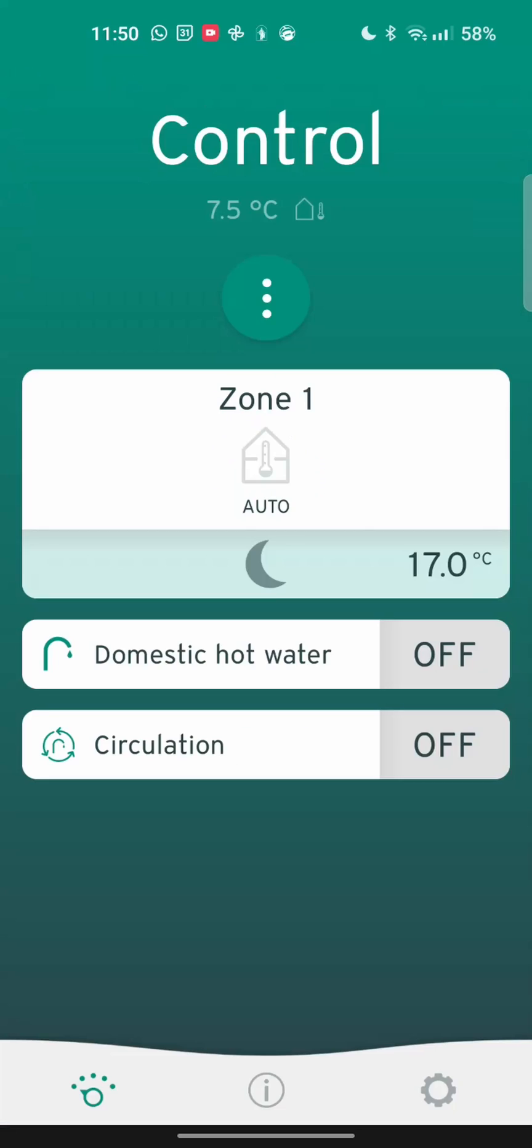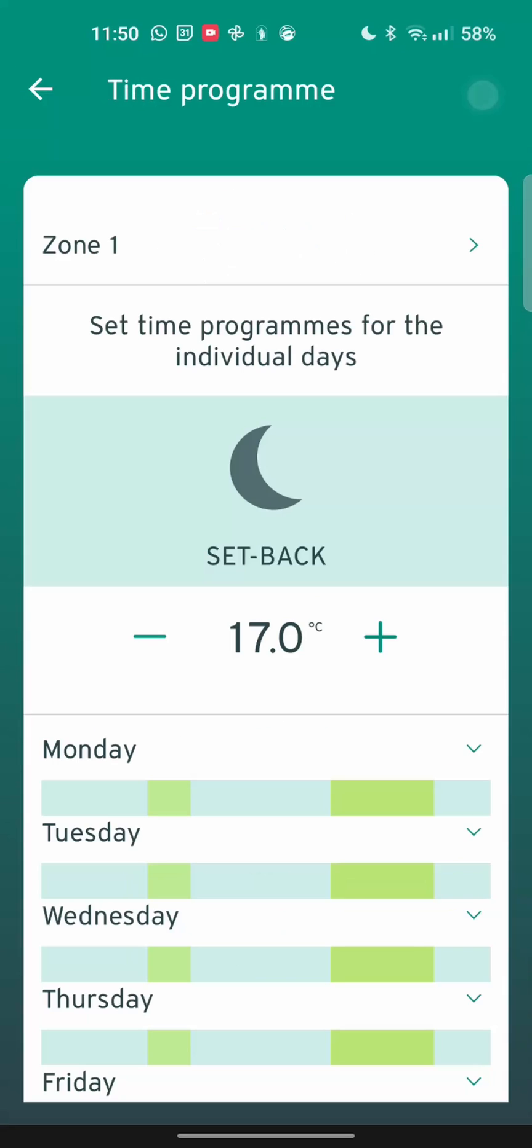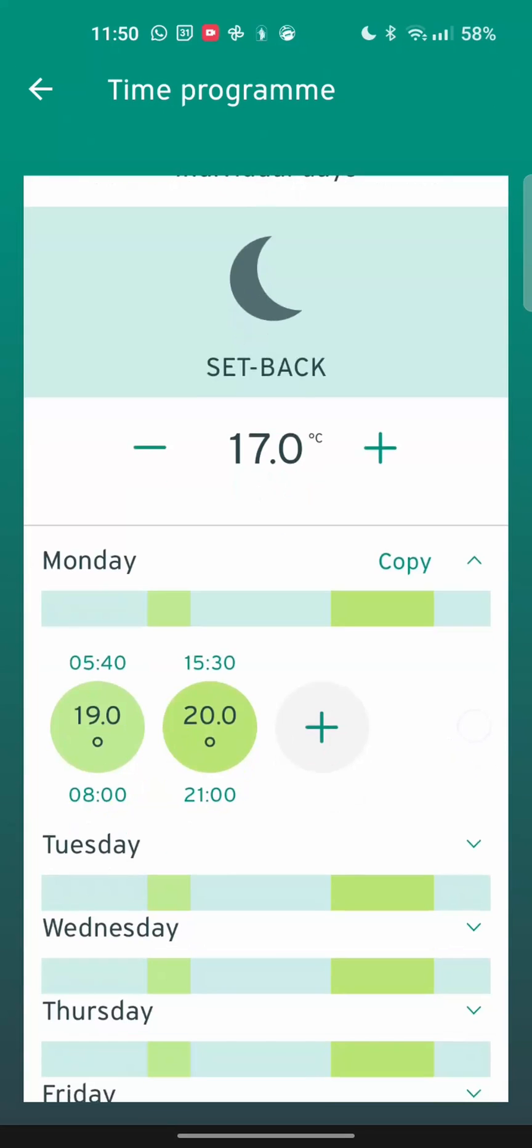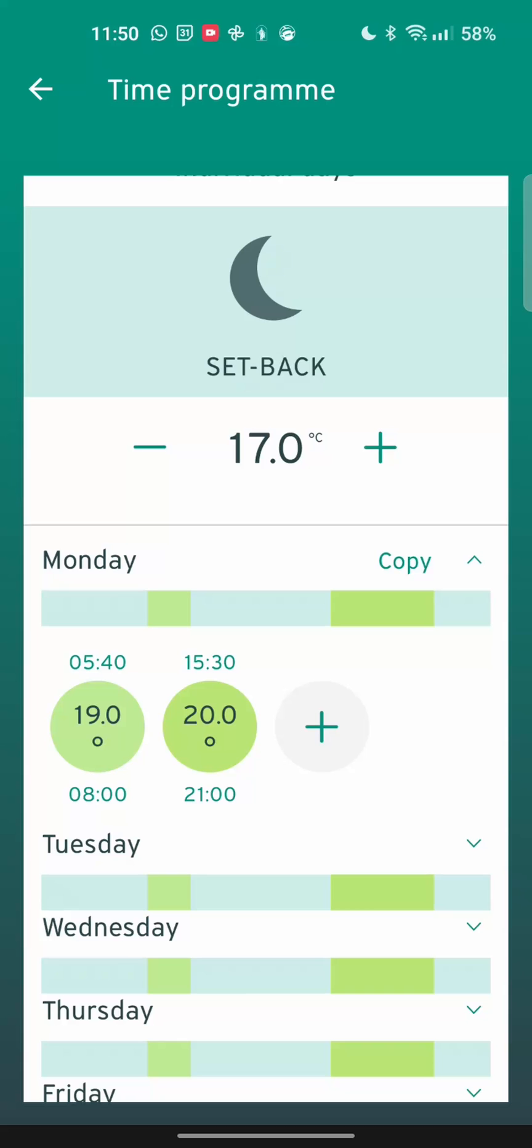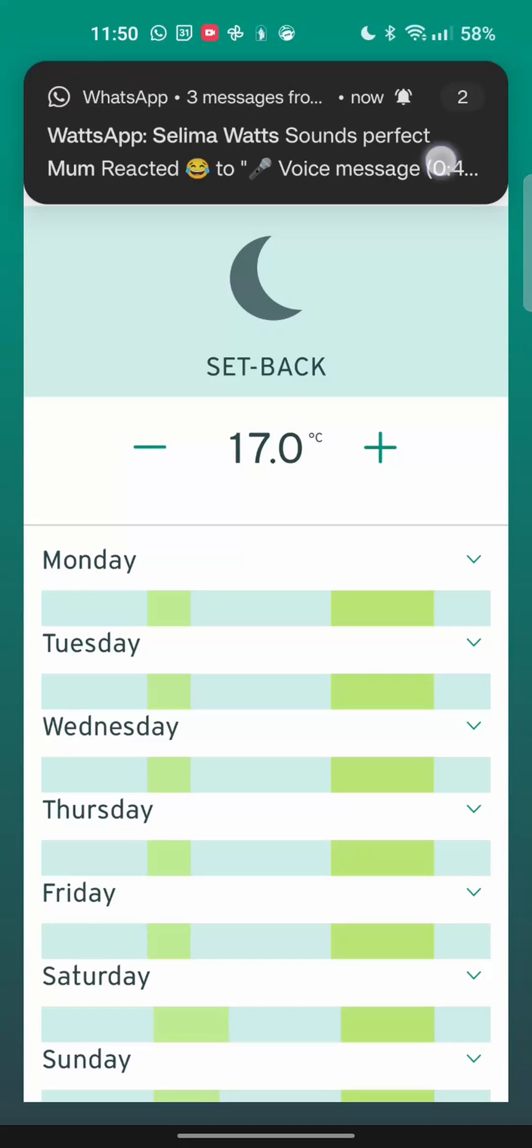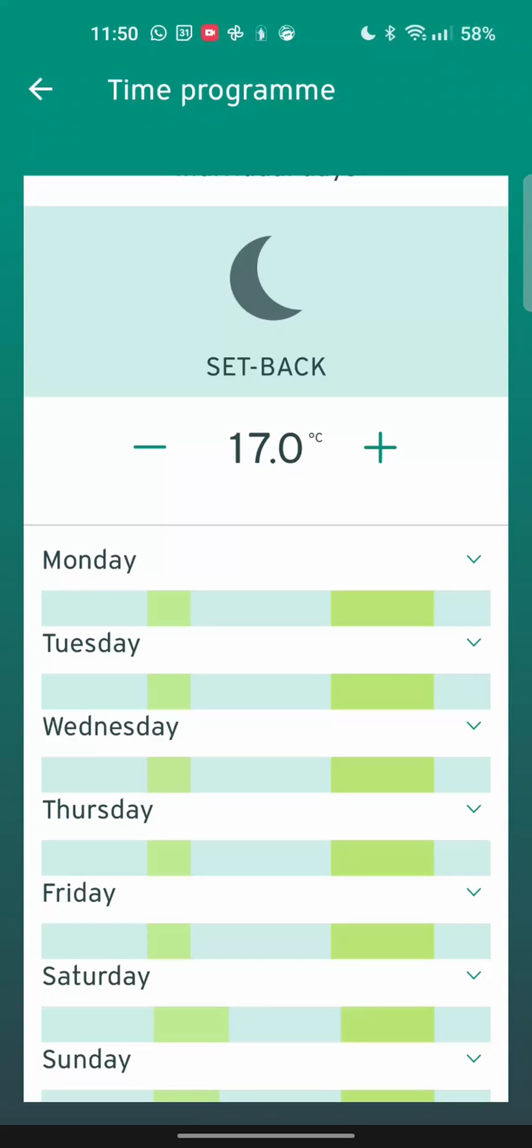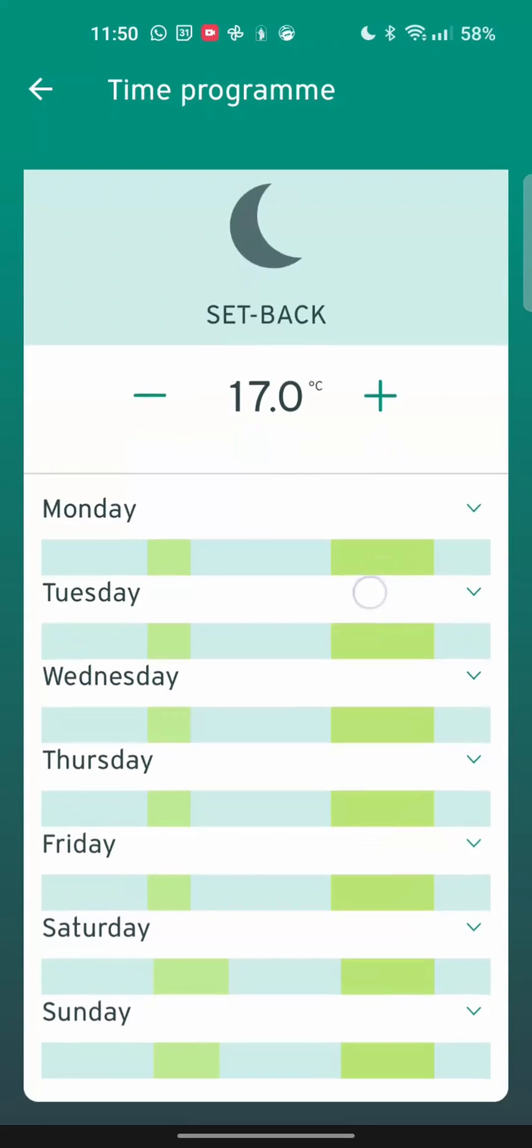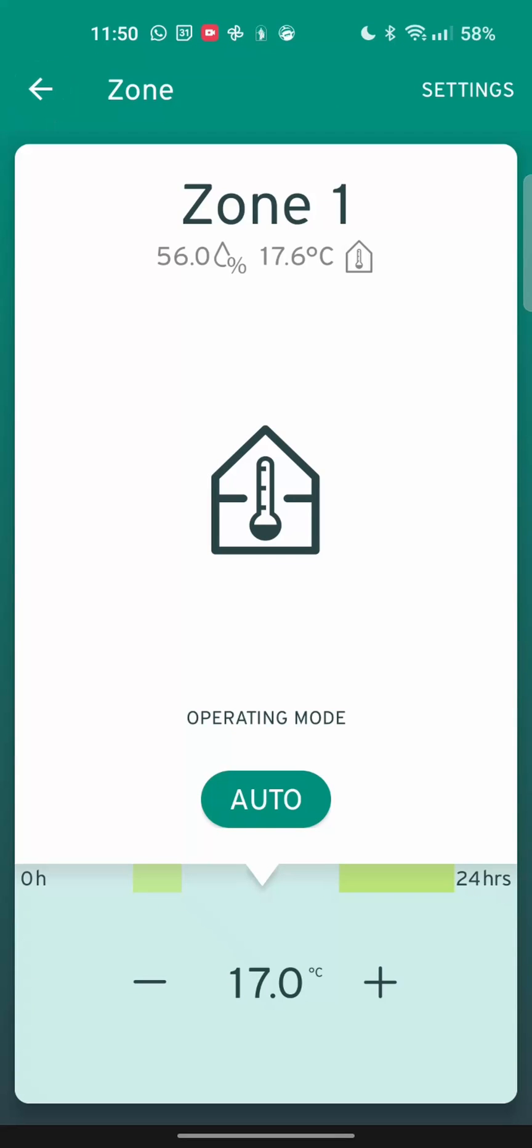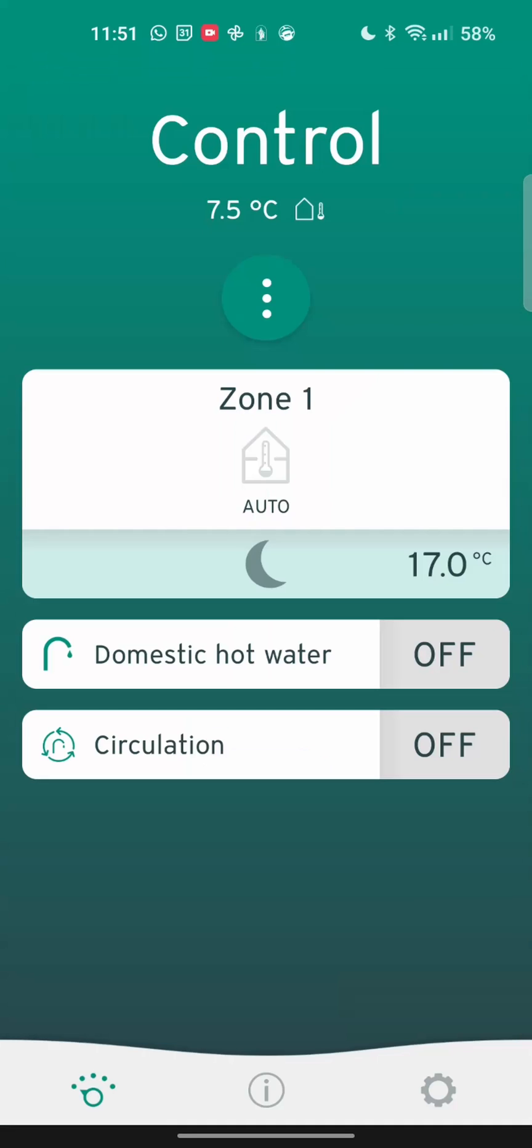The reason I do that is because if you look at our timer for our heating zones, it turns off at nine o'clock. So the heat pump can switch the valve straight away and it's already up and running. It will have to raise the flow temperature for heating the water, but it's not starting from completely dead. That does appear to be giving me slightly better efficiency working that way.